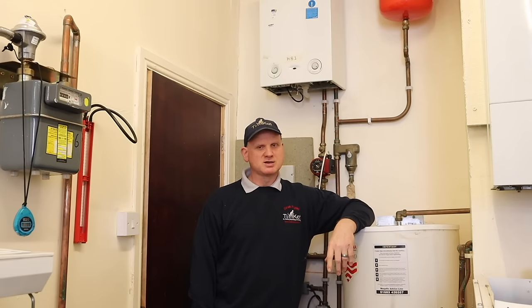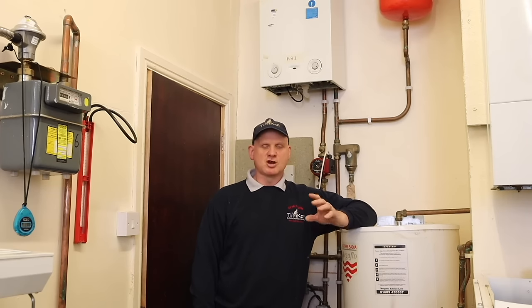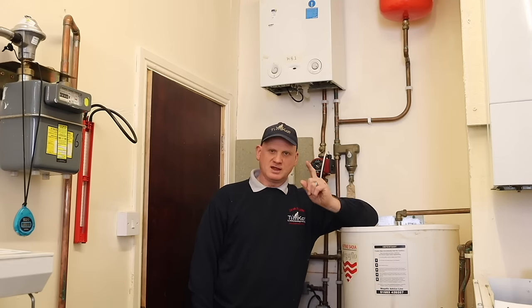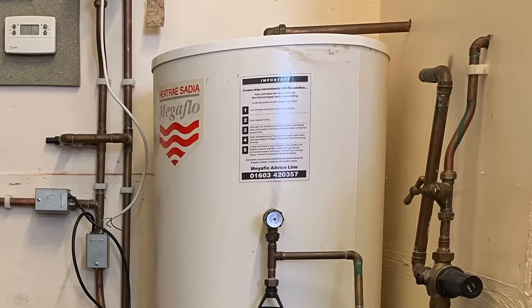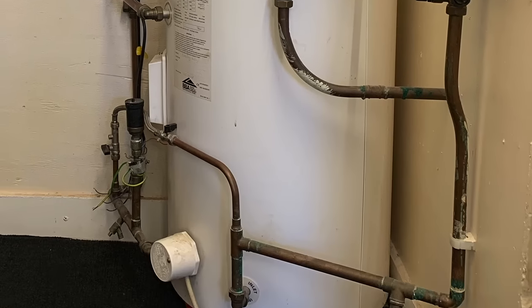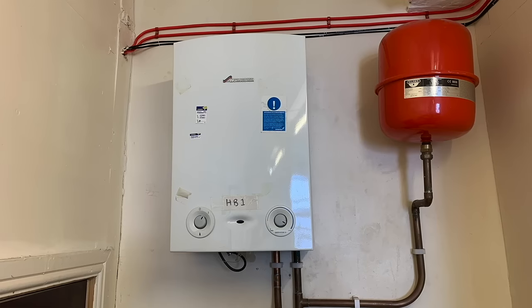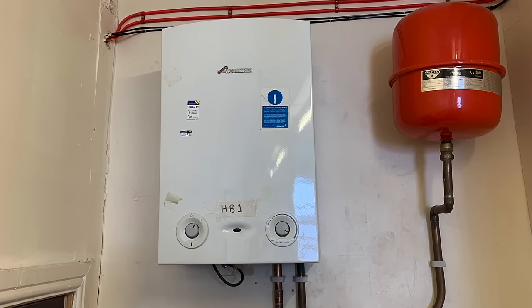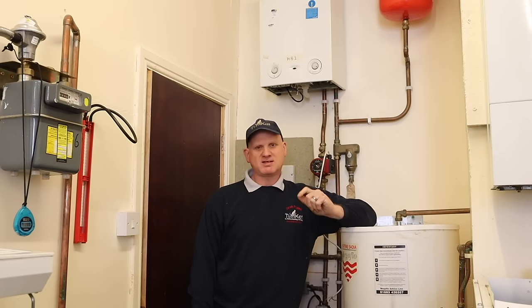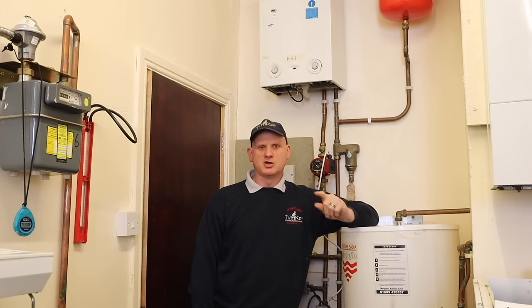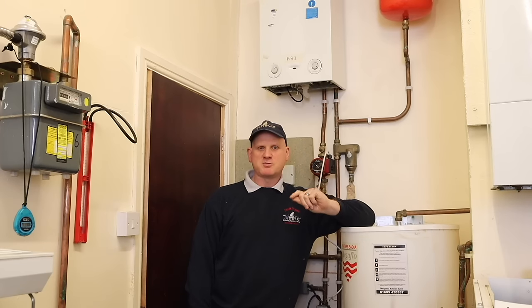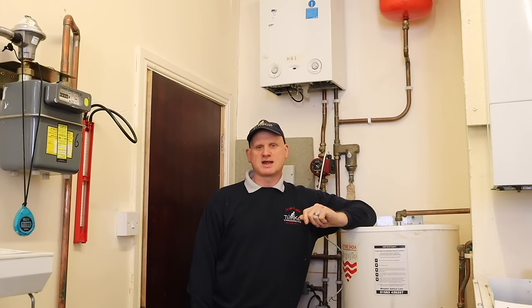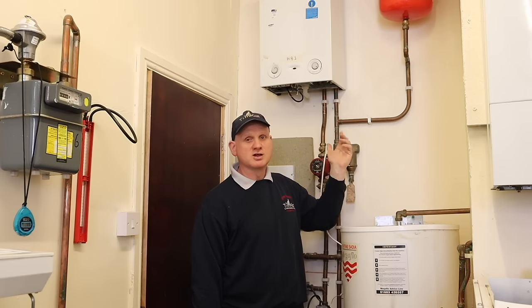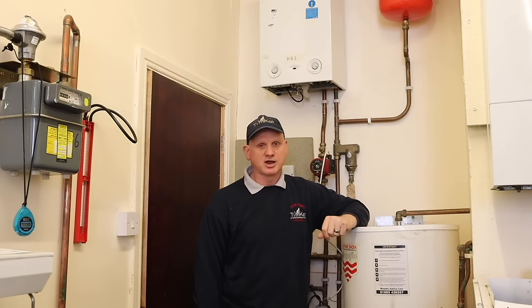However, combination boilers are not very good at coping with two showers running at the same time due to the usage of the water across the two showers. If this is the case, then this, which is an unvented hot water cylinder, and this above me, which is a heat-only boiler, you could actually use a system boiler, would be a better choice rather than a combi boiler for your property. So if you've got two bathrooms where you want to run two showers at the same time, then this is what you're going to be requiring, not a combi boiler.